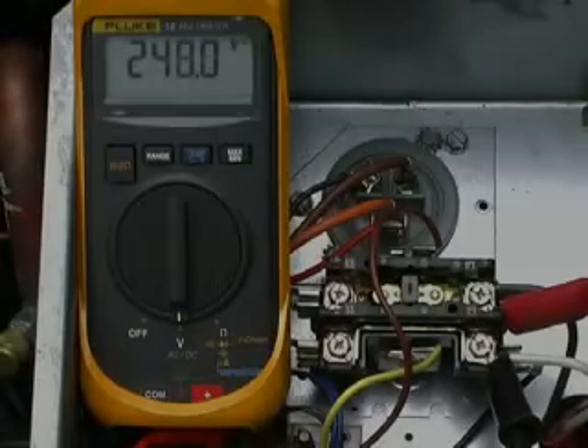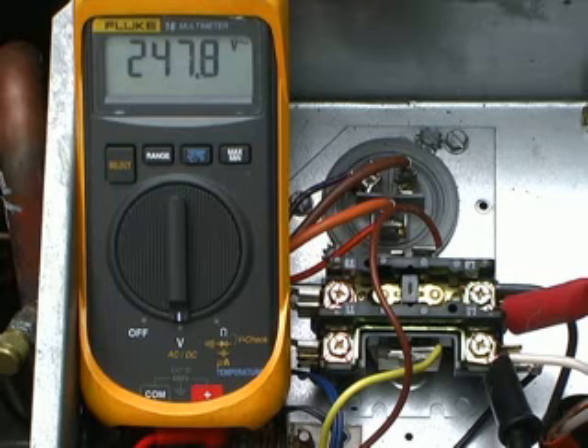And of course, the other situation is the contactor's pulled in but nothing's running. In a case like that, I'll say there are three possibilities: no voltage coming into the bottom of the contactor; no voltage going out of the contactor, which means the contacts are messed up; or voltage coming out of the contactor and still nothing running, which means the motor and compressor circuits have to be open somewhere.